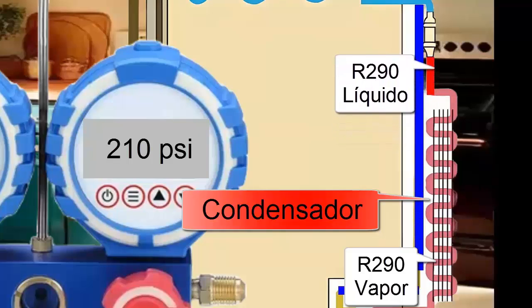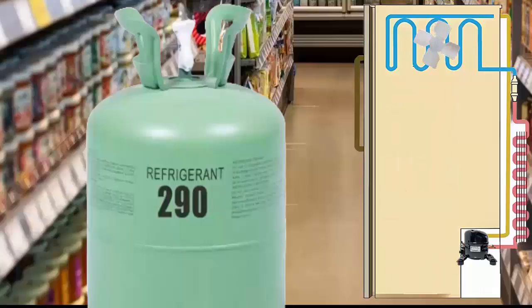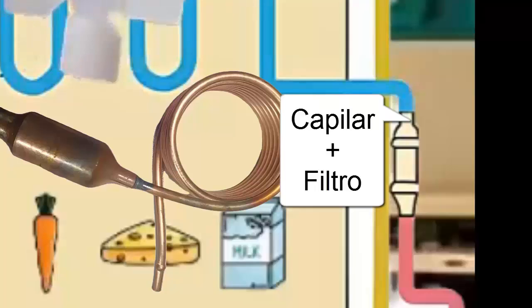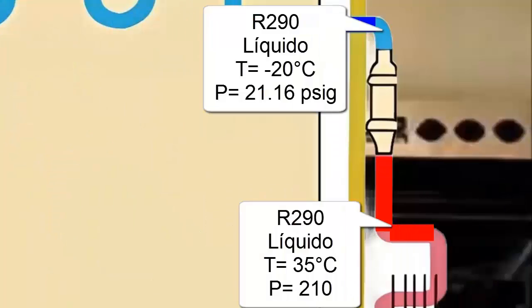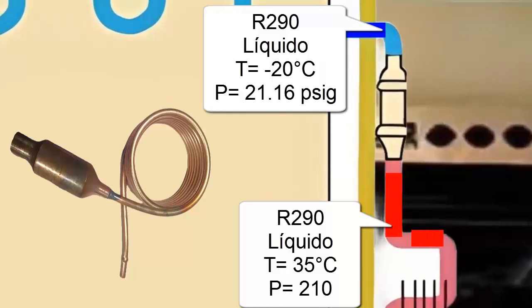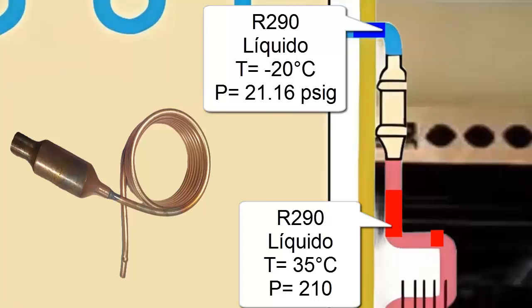The R290, now in a liquid state and at a temperature close to the ambient temperature, exits the condenser and moves to the capillary tube to restart the cycle. In the capillary tube, the pressure and temperature of the refrigerant decrease significantly, so it returns to the initial pressure of 21 pounds per square inch and minus 20 degrees Celsius.